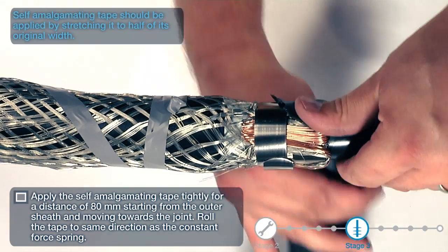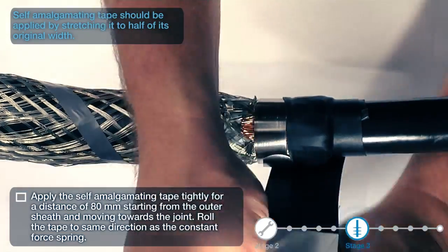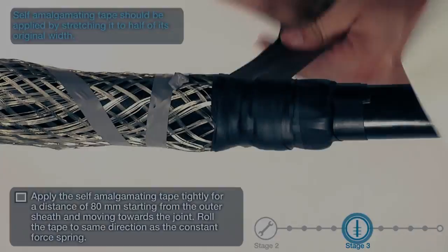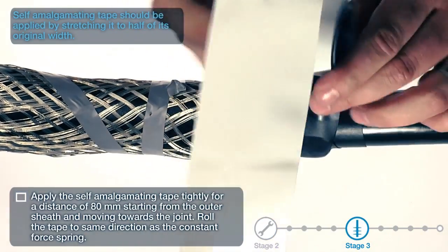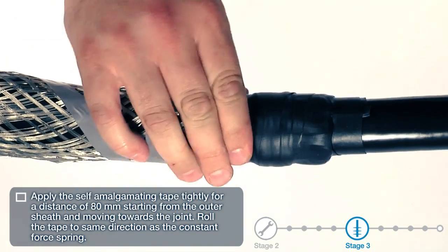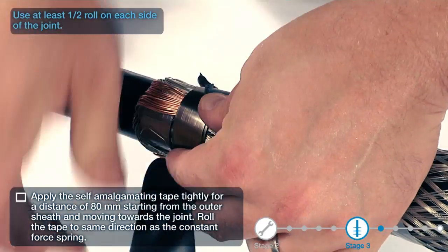Apply the self-amalgamating tape tightly for a distance of 80 millimeters starting from the outer sheath and moving towards the joint. Roll the tape to the same direction as the constant force spring. Self-amalgamating tape should be applied by stretching it to half its original width. Use at least half a roll on each side of the joint.